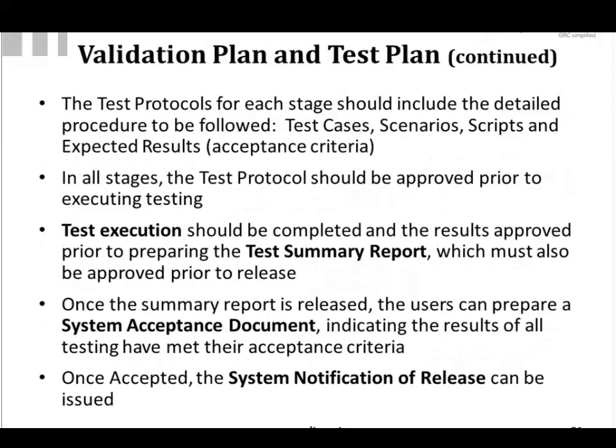Test protocols should include detailed procedures. So you start with your test cases and scenarios, which are your situations, what would be going on in your particular area of work. Then scripts that are more specific that detail the steps to be taken for those cases. And also list out the expected results, and that should be based on acceptance criteria.